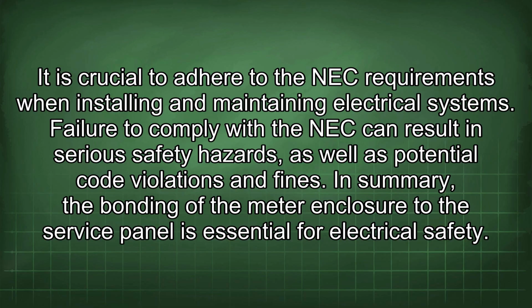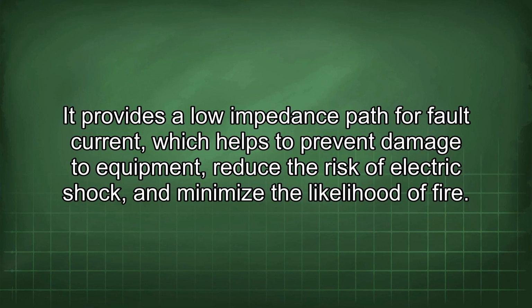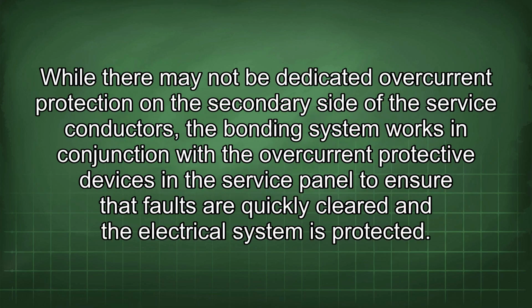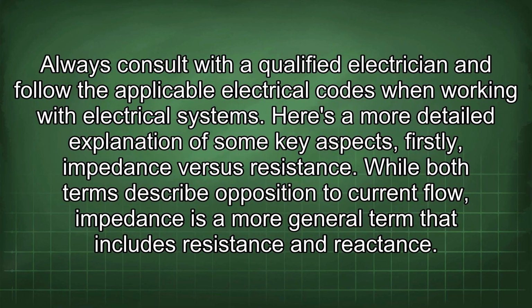In summary, the bonding of the meter enclosure to the service panel is essential for electrical safety. It provides a low impedance path for fault current, which helps to prevent damage to equipment, reduce the risk of electric shock, and minimize the likelihood of fire. While there may not be dedicated overcurrent protection on the secondary side of the service conductors, the bonding system works in conjunction with the overcurrent protective devices in the service panel to ensure that faults are quickly cleared and the electrical system is protected. Always consult with a qualified electrician and follow the applicable electrical codes when working with electrical systems.